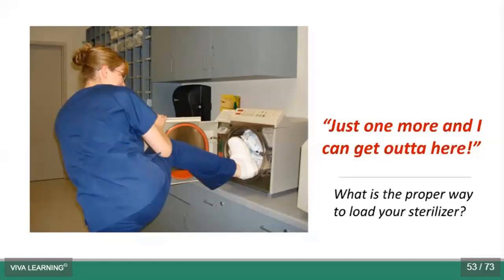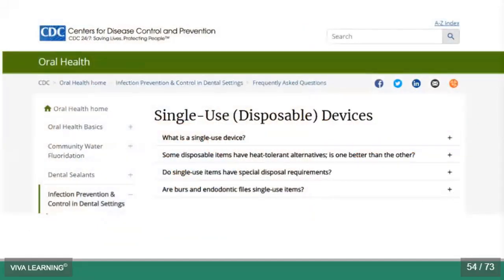Okay, and this is where it's kind of a trick response, right? Because ideally it's actually on its side, but your manufacturer's IFU for your sterilizer may say paper side up or paper side down. And I will tell you that you want to follow the manufacturer's IFU, but the majority of the steam sterilizers, the IFUs that I have read, have said they want you to load your instruments, your PeelVue pouches, paper side down in the sterilizer. But I'm not going to tell you which one wants them up and which ones want them down, because I want you to refer to the IFU for your particular sterilizer.